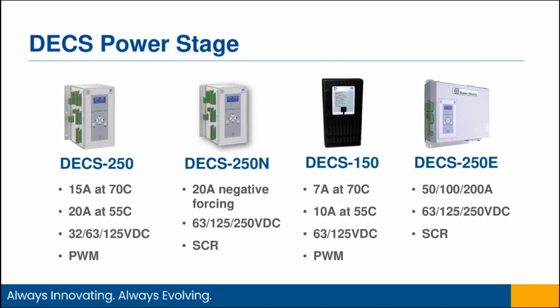So this next slide shows an overview of our DECS line of voltage regulators and what their power stages are. We have two on this list that are pulse width modulated, or use that IGBT output, and then we have two that are SCR outputs. At various current levels, depending on your application, you may need higher or lower excitation levels, hence the difference between all the models. We have the DECS 250, which is a 15 amp power stage, pulse width modulated. Then we have our DECS 250N, which is an SCR based power stage.